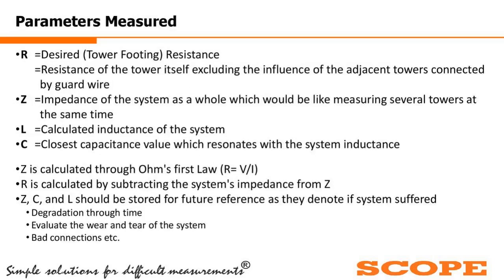Now, the instrument gives some parameters on the display of this tower footing resistance meter. The 4 parameters displayed are: R, the desired tower footing resistance; Z, the impedance of the system; L, the calculated inductance of the system; and C, the closest capacitance value which resonates with the system inductance. These are the 4 parameters, and some people have asked me about them over the phone at different times, so I want to clarify that point also.